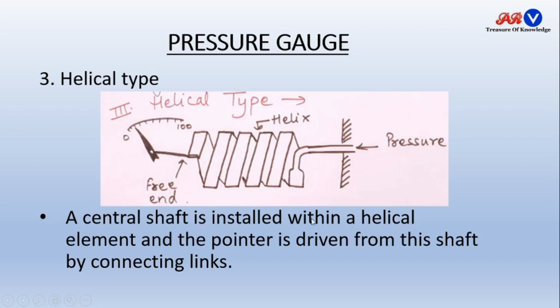Here a center shaft is installed within a helical element. This is the helical element, and at the free end the center shaft is inserted, and the pointer is driven from this shaft. When this end moves, the pointer will move on a scale which is calibrated in terms of the pressure. In this way it will give pressure. The only advantage of this tube is that there is no need of the geared sector and pinion arrangement and amplification of the displacement.